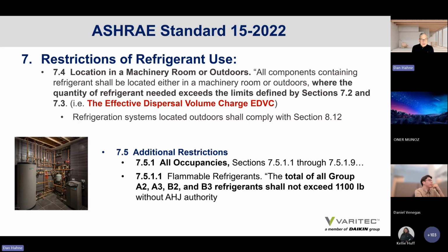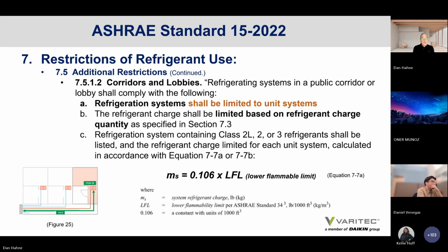There are also additional restrictions under section 7.5 regarding occupancies and flammable refrigerants not exceeding 1,100 pounds without an authority having jurisdiction for a building. There are additional restrictions for VRV systems that serve corridors and lobbies. Refrigeration systems shall be limited to unit systems. They will have their own assigned condenser. The refrigerant charge shall be limited based on refrigerant charge quantity. The refrigerant system containing A2L, A2, and A3 refrigerants shall be listed, and the refrigerant charge limited for each unit system calculated in accordance with equation 7-7A. So laying out a system for a corridor, you would use equation 7-7A to assign what that refrigerant quantity is serving that corridor.